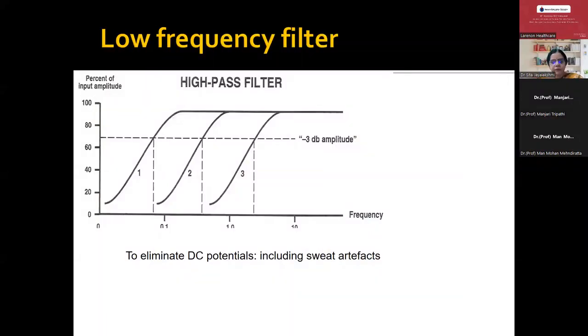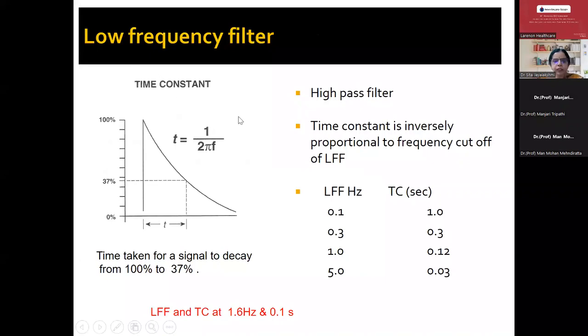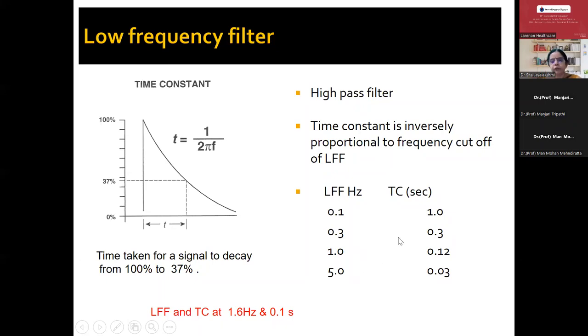The second is the low frequency filter, which is important to eliminate direct current potentials — especially sweat artifacts. The low frequency filter is also known as the high-pass filter. There is an important relationship between time constant and the low frequency filter in the EEG machine — both are inversely proportional. The time constant is inversely proportional to the frequency cutoff of the low frequency filter. Normally we keep the low frequency filter with a time constant of 0.1. Time constant is the time taken for a signal to decay from 100% to one third — that is, 37%.